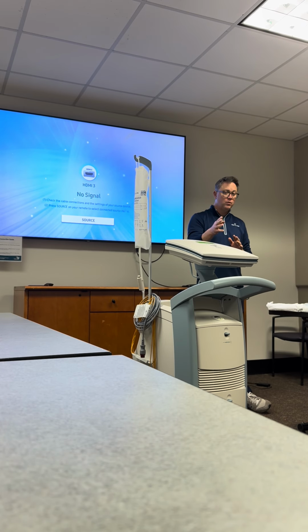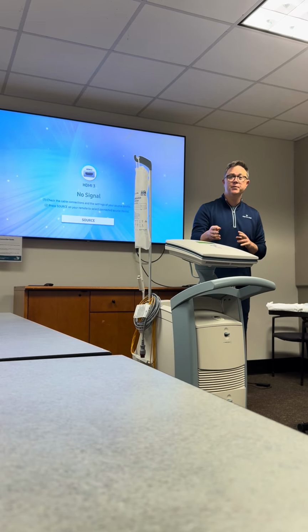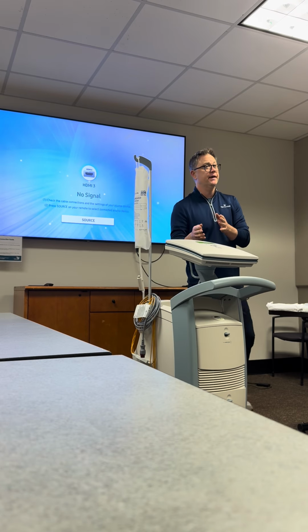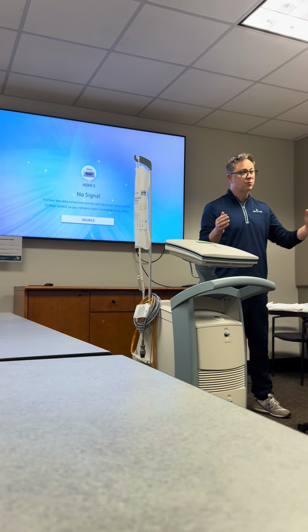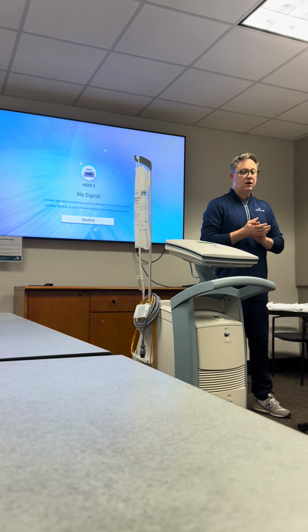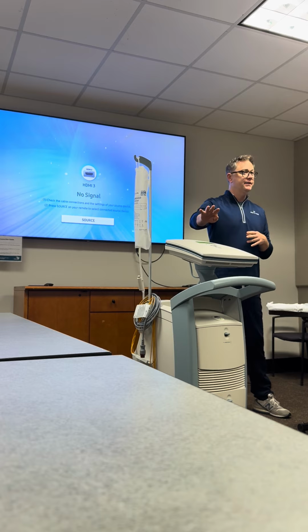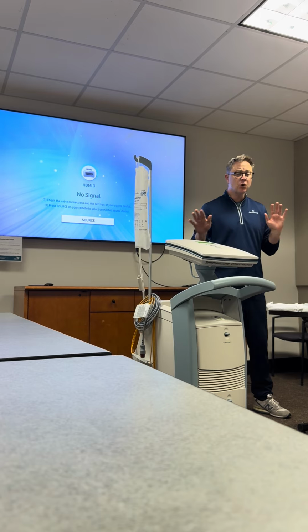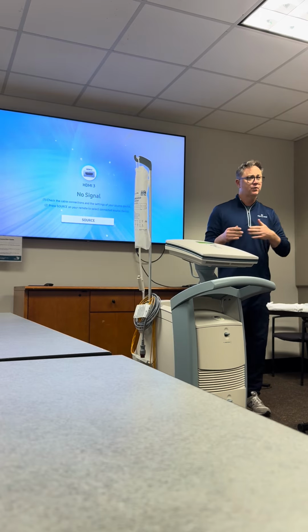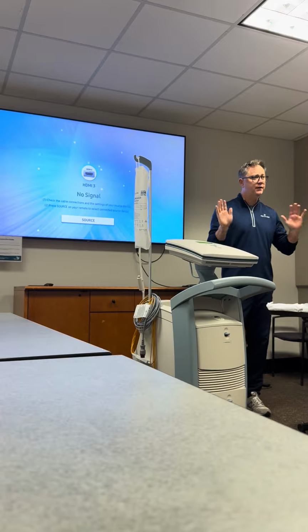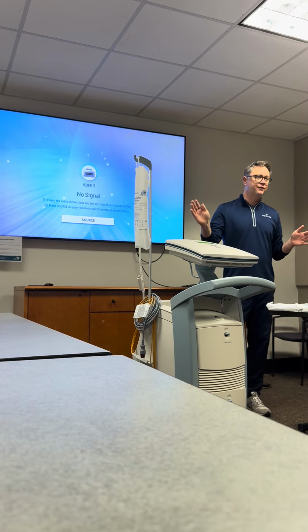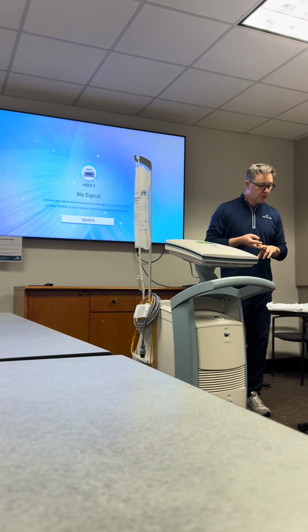The balloon pump prefers the ECG signal because the electrical signal comes before the mechanical signal of that upstroke of systole. It just gives it more time to set up its timing. So once you're able to get leads on, the balloon pump will switch over to that EKG trigger. Totally safe to run the patient in either one. You could run a patient in pressure trigger the whole run. Again, the balloon pump just prefers the EKG because it just gives it more time to set up its timing. So those are the two primary triggers.